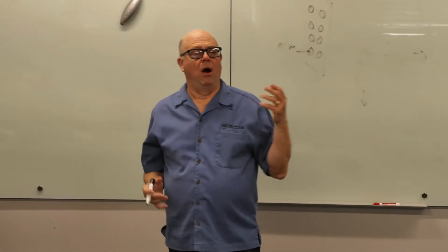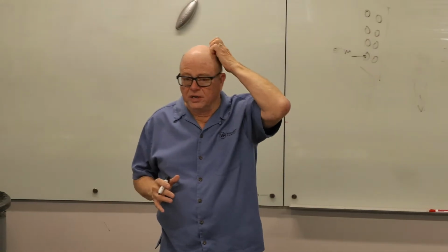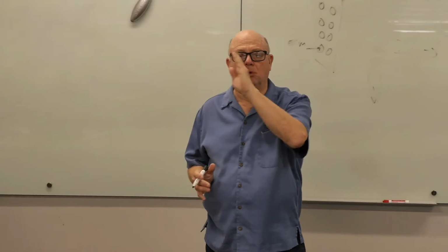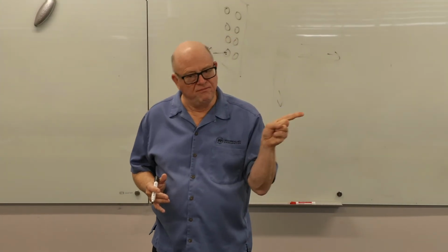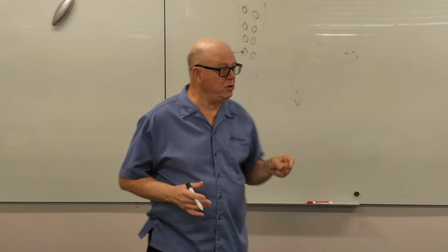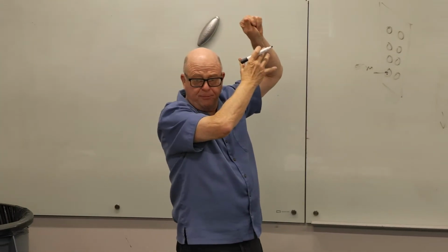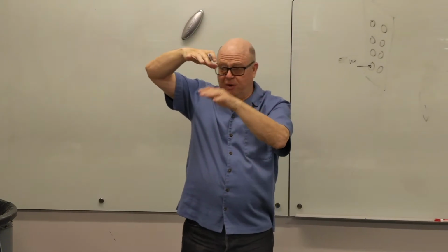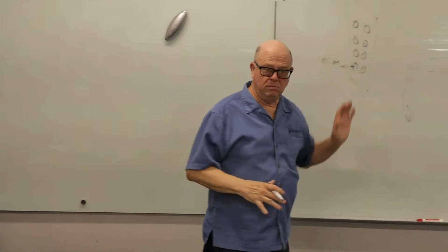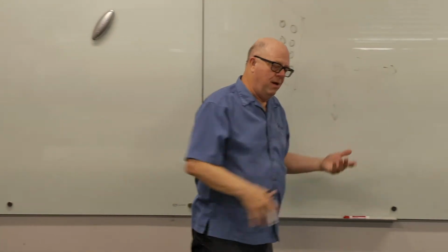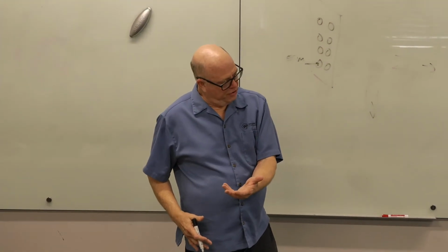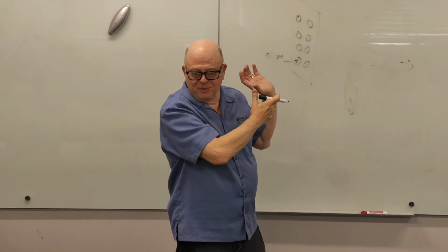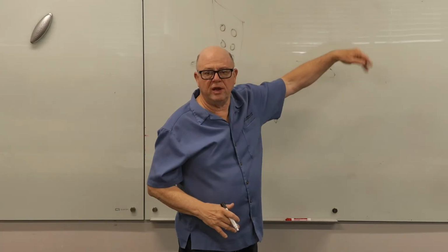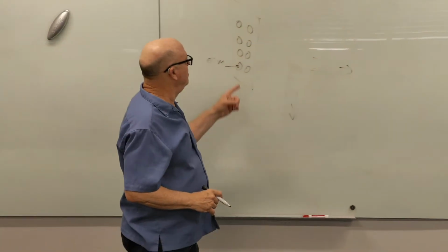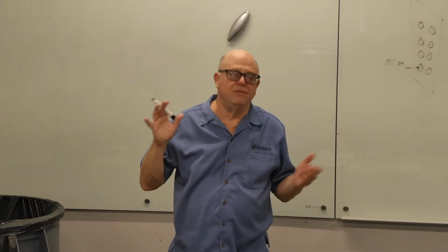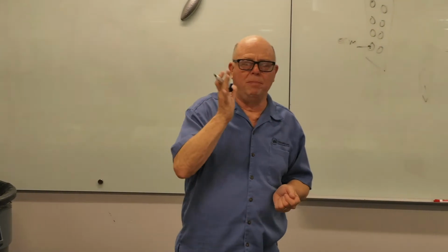ECM motors, the easiest way to think of an ECM motor is that it's a multiple speed motor, not a variable speed motor. When you take a standard motor and you put a variable speed drive, it changes the hertz like we were talking about, in an analog manner. This digital device, the variable speed drive, changes the hertz and therefore changes the motor speed. ECM motors don't work that way. The easiest way to think of them is they have a whole bunch of speeds.